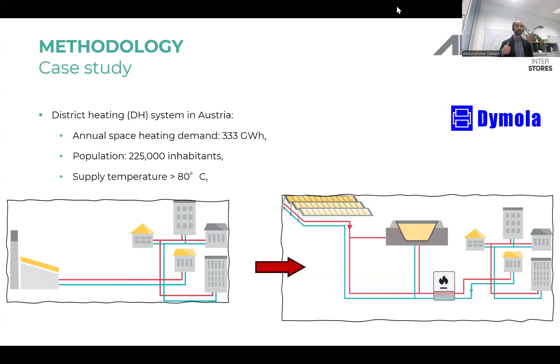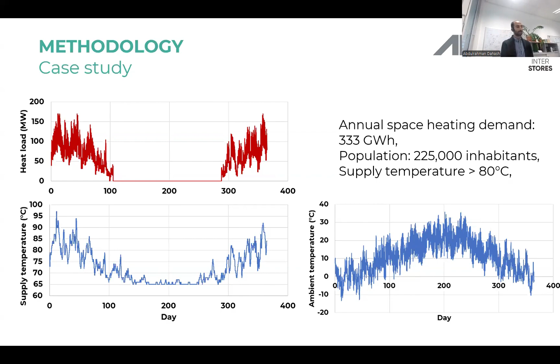As you see here, we have the boundary conditions from the district heating system. On the top left, the red line shows the heat load, focusing only on the space heating load. That's why during summer we have 0, and the load peaks at around 165 megawatts. On the bottom left, you find the supply temperature. During summer, it's almost constant at 65 degrees Celsius due to the Legionella constraint. And here we have the ambient temperature.